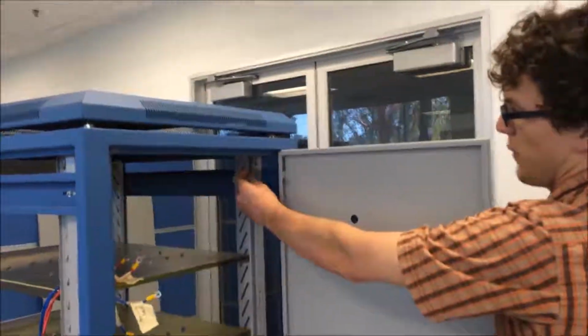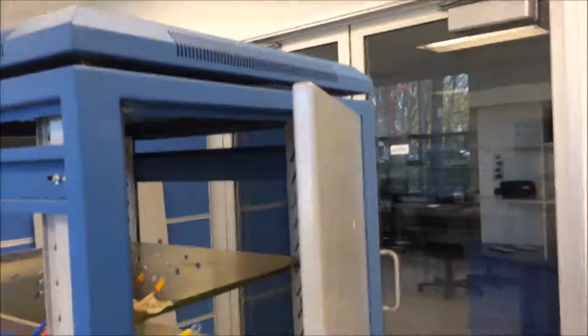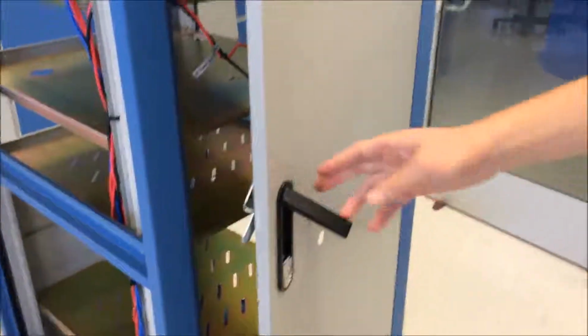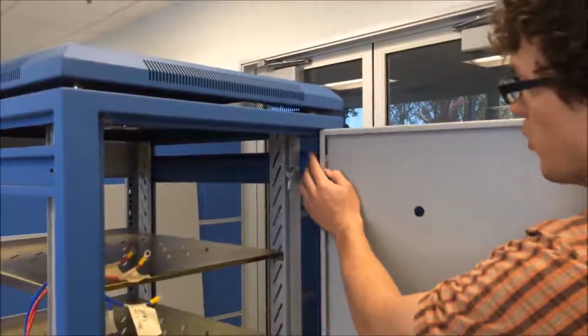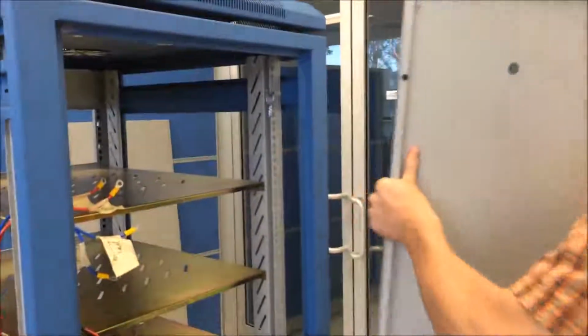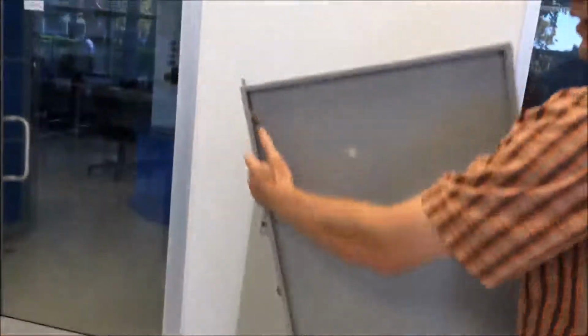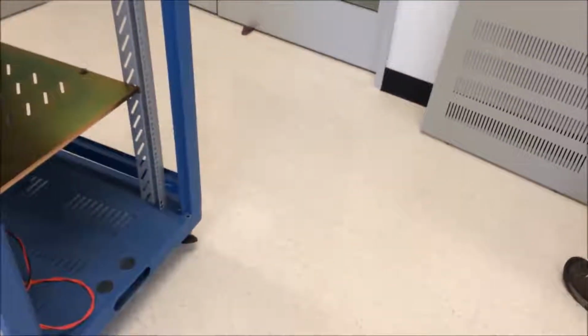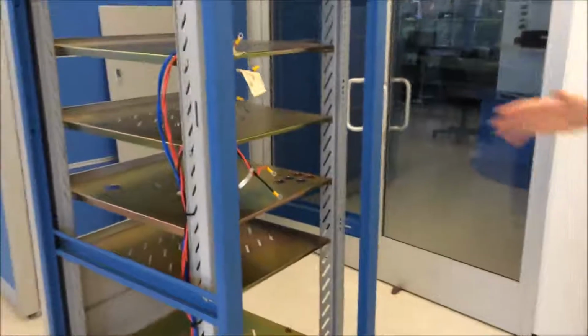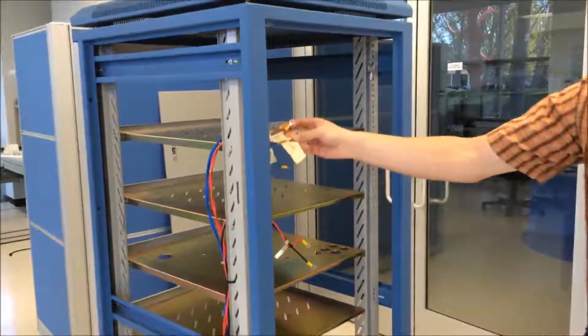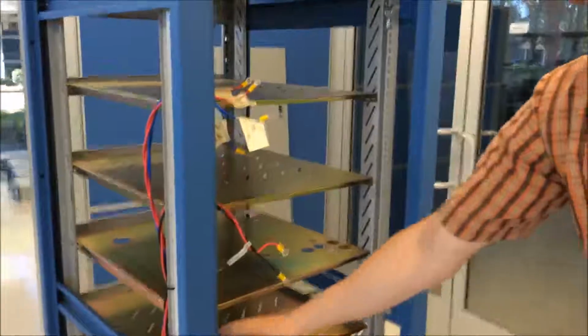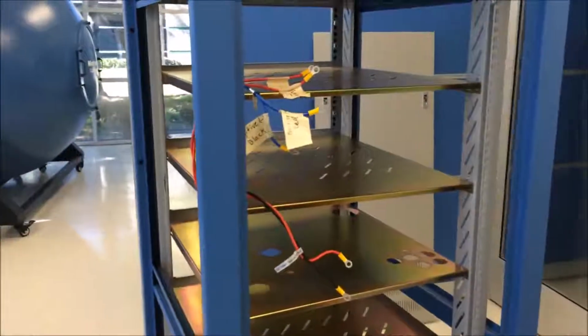You can see here that there are a pair of keys. You can use those to lock the cabinet if you don't want people having access to the instruments. I'm going to pull the door all the way off for now. And that's done just by pushing this down and then sliding it out and pulling it up. There's another on the bottom. So as you can see, we will pre-install all of these cables to make it slightly easier.